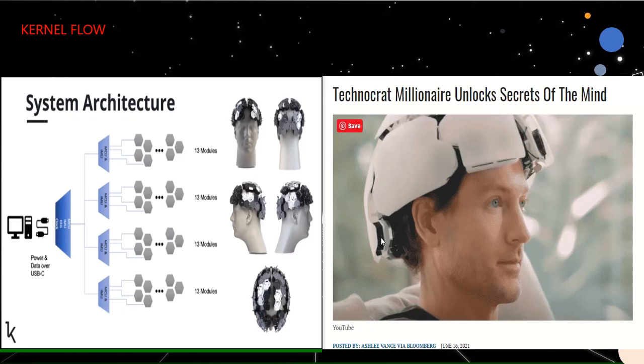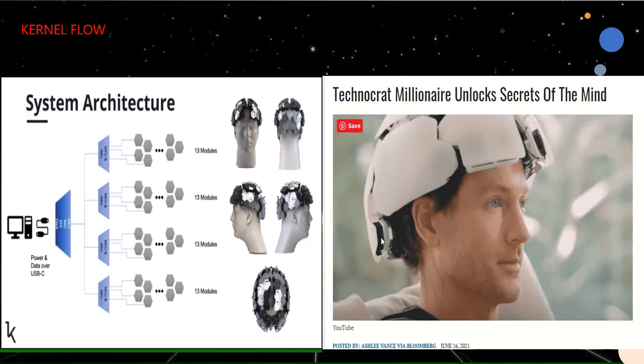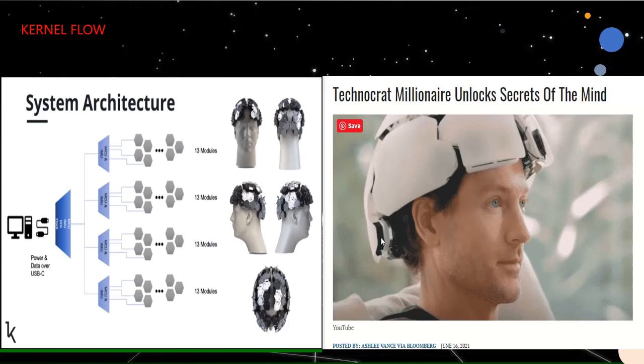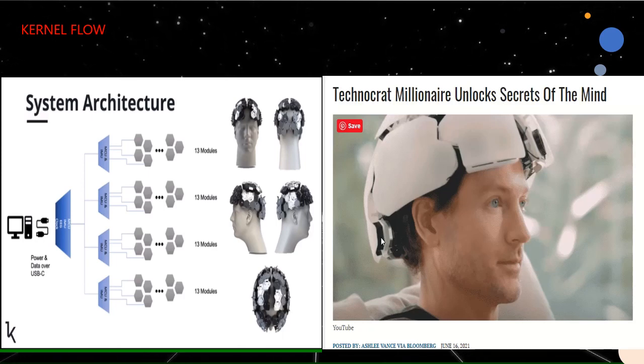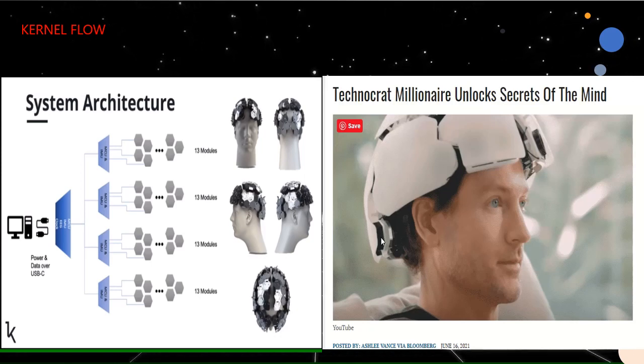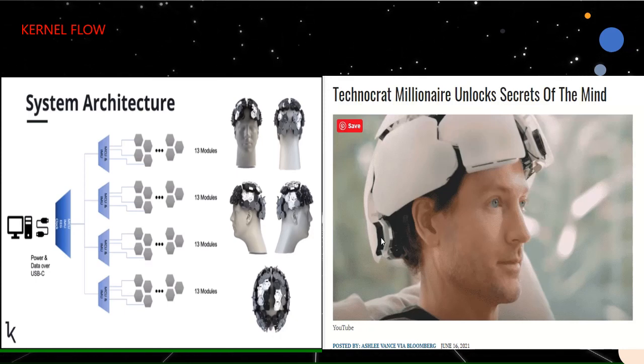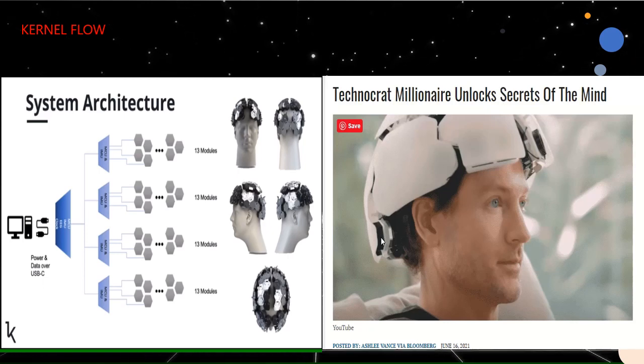All of the 52 modules in the system are synchronized to a common global clock reference to enable precise time alignment between all lasers and detectors in the system. In addition to these optical sensors, each microcontroller is paired with an inertial measurement unit, and the primary microcontroller assembly includes an 8-channel EEG front-end and ADC for interfacing with dry active electrodes. Power and data are transmitted throughout the system over a wiring harness that connects all modules and microcontrollers together.